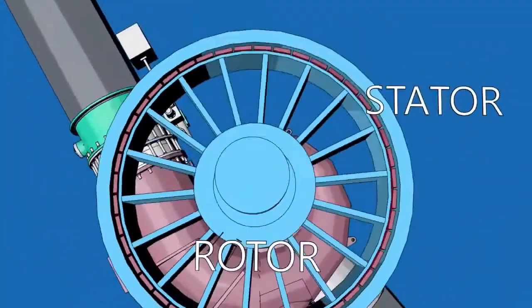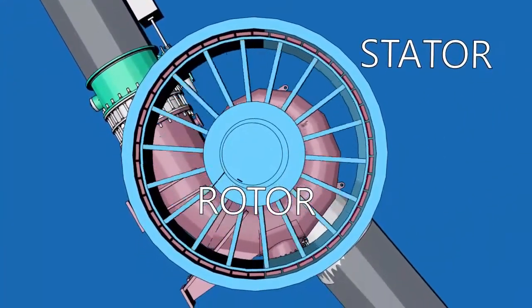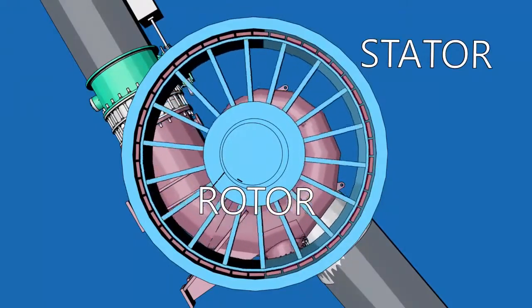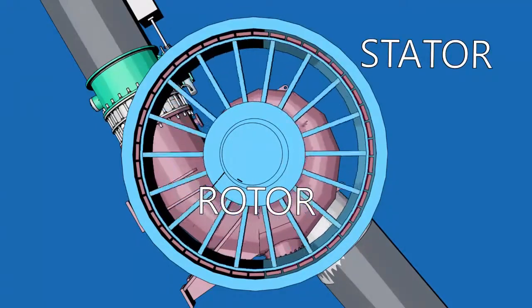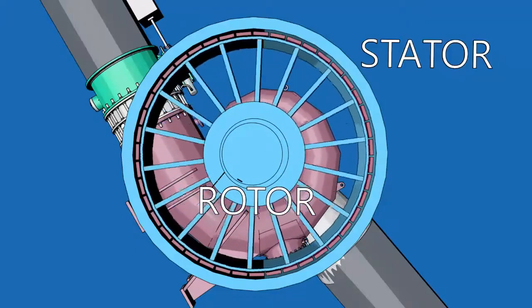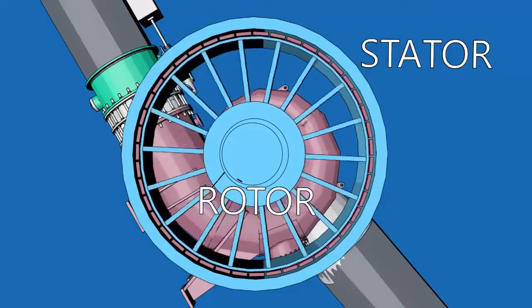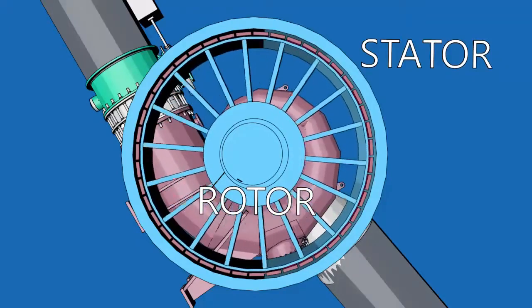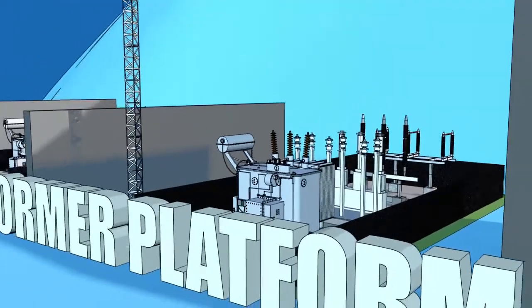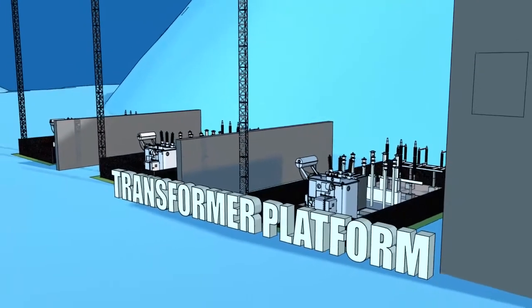The turbine is coupled to the generator via a shaft, and as it rotates, the rotor, the rotating part of the generator, cuts the magnetic field of the stator, the stationary part of the generator. As the rotor cuts the magnetic field, alternating current is generated and stepped up to 330 kilovolts for transmission.